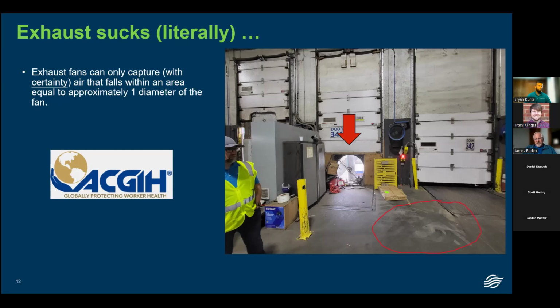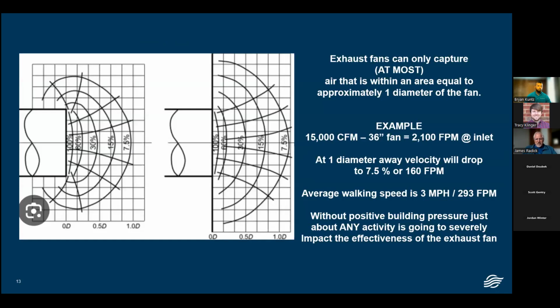of the opening. I'm going to show you the American Council of Industrial Hygienists, a lot smarter folks than I am. They've got it defined there, and they've got some great graphics I'm going to share with you in a moment. But what I want to really stress here is you've got the negative on the building. You've got an exhaust fan running, and the stuff that's circled on the floor is the dirt and whatnot that's being produced. The exhaust fan is that close to it. If it can't capture dirt and contaminants that are that close to it, general exhaust doesn't have a prayer of picking up any contaminants that are outside of one diameter of the fan. So the next screen is taken from the Government Hygienist's Handbook.